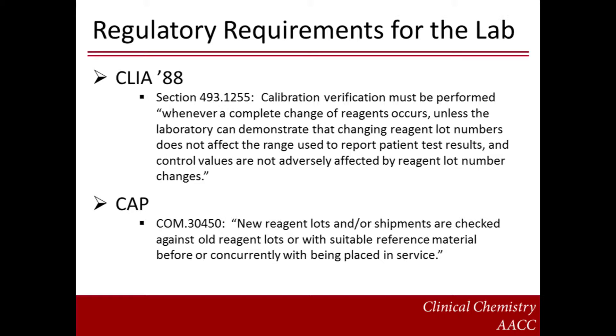Historically, laboratory validation practices were highly variable, and some laboratories did not do any validation at all. CLIA 88, however, stipulated that calibration verification must be performed whenever a complete change of reagent occurs, unless the laboratory can demonstrate that changing reagent lot numbers does not affect the range used to report patient test results, and control values are not adversely affected by reagent lot number changes. The enactment of CLIA 88 in 1992 thus led to the inclusion of reagent lot validation requirements in the accreditation checklist of numerous professional organizations. For example, Standard COM 30450 in the All-Common Checklist of the College of American Pathologists specifies that new reagent lots and/or shipments must be checked against old reagent lots or with suitable reference material before or concurrently with being placed in service.